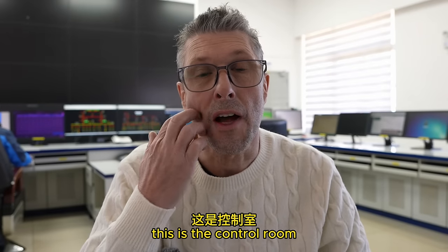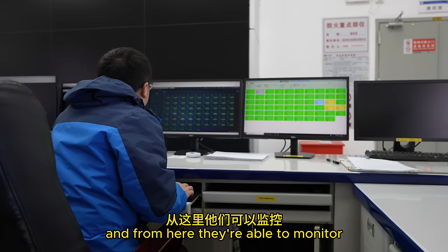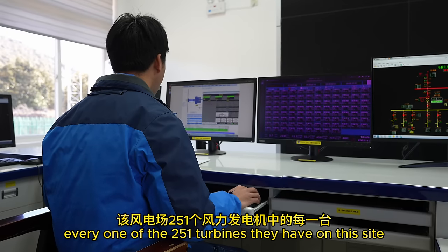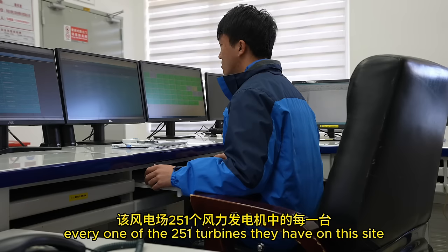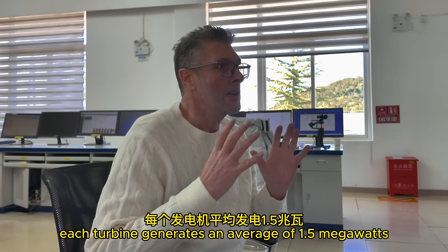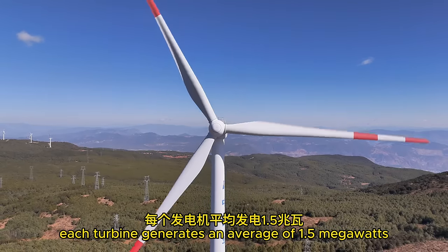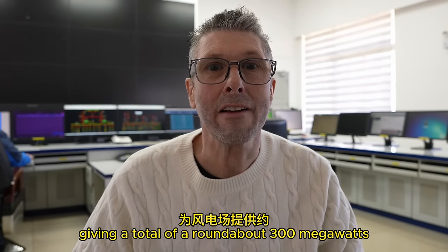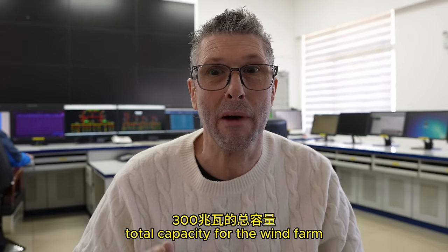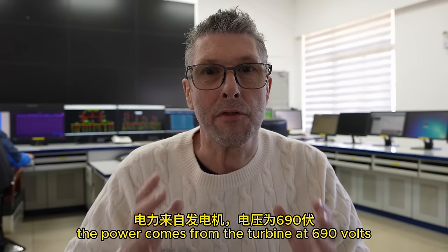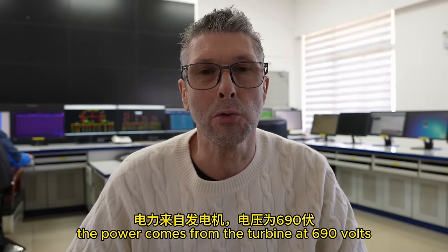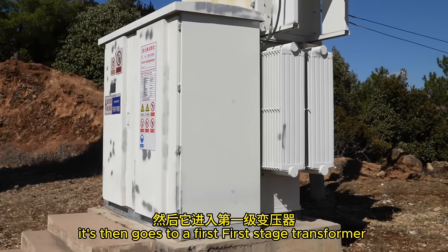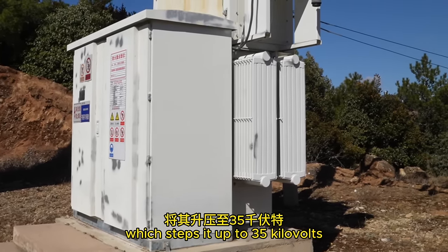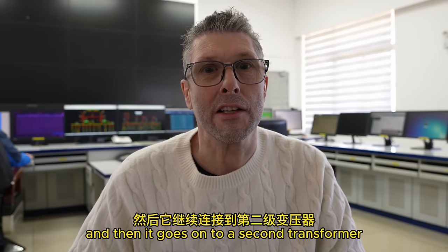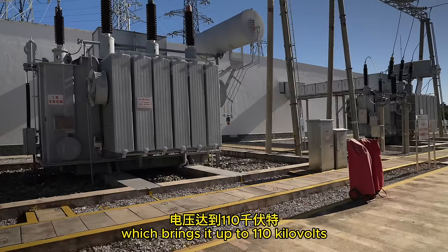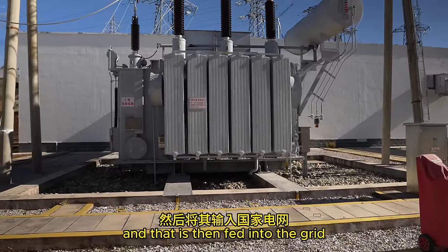This is the control room, and from here they're able to monitor every one of the 251 turbines on this site. Each turbine generates an average of 1.5 megawatts, giving a total capacity of around 300 megawatts for the wind farm. The power comes from the turbine at 690 volts, then goes through a first stage transformer which steps it up to 35 kilovolts, then a second transformer brings it up to 110 kilovolts, and that is fed into the grid.